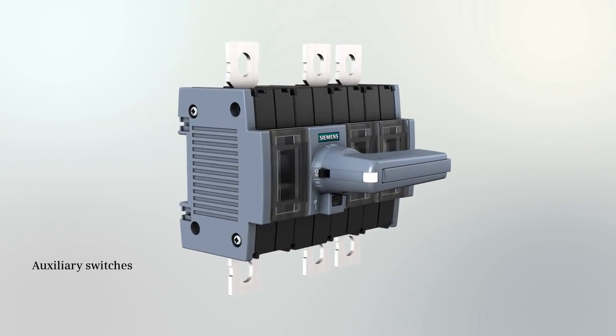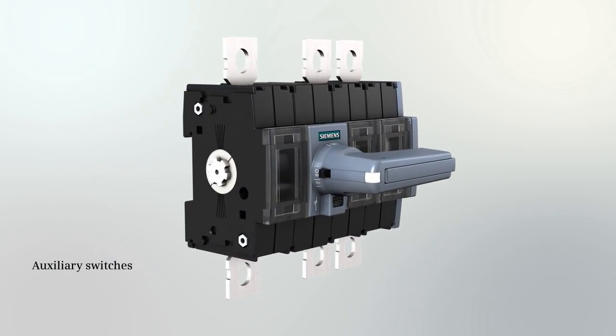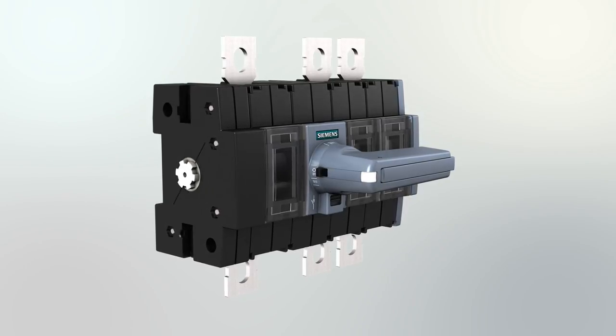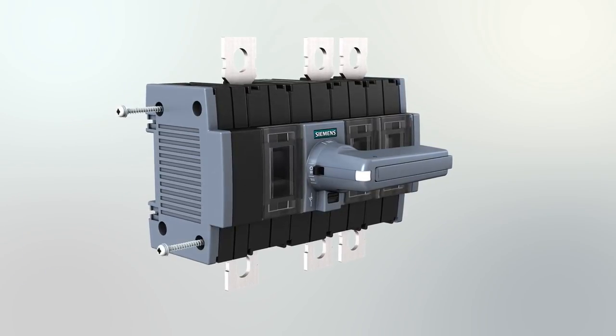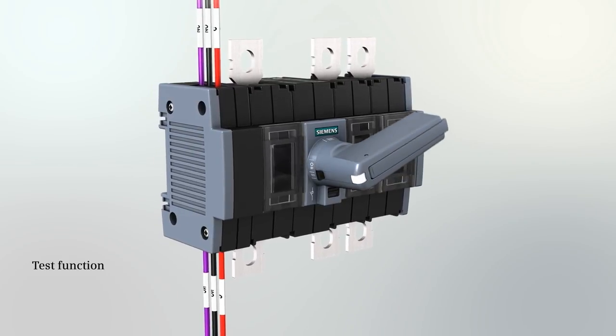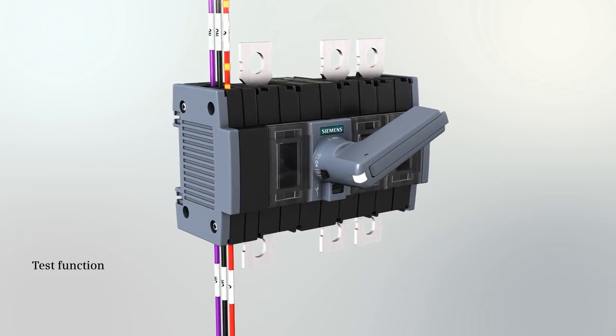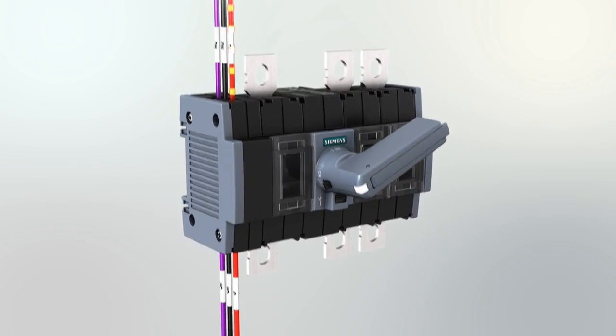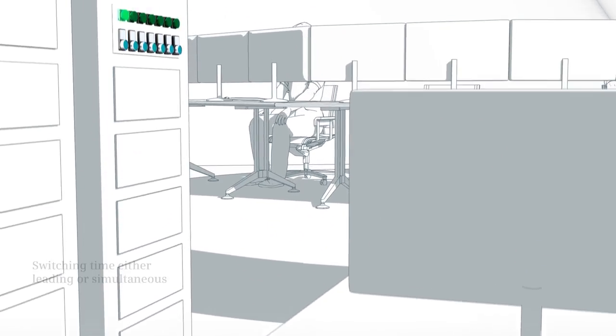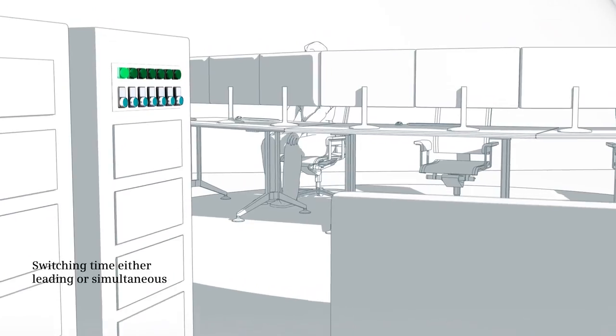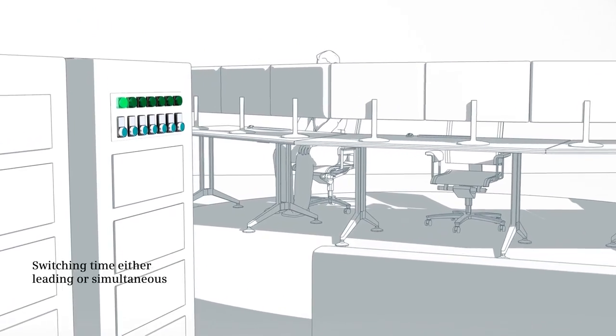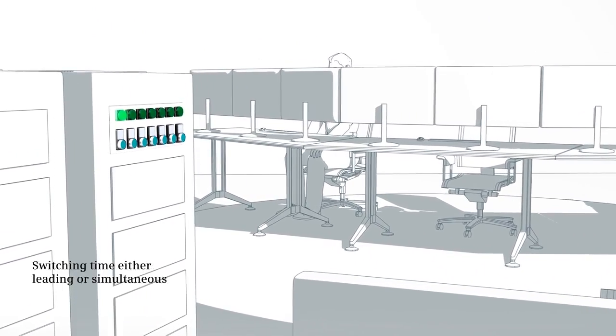Auxiliary switches of 3KD switch disconnectors allow feedback about the switching status, for example, to a control room. In addition, the test function of the auxiliary switches allows checks of the control circuit, without the need to close the main contacts. With all sizes, the auxiliary switches can switch either simultaneously with the main contacts or leading.